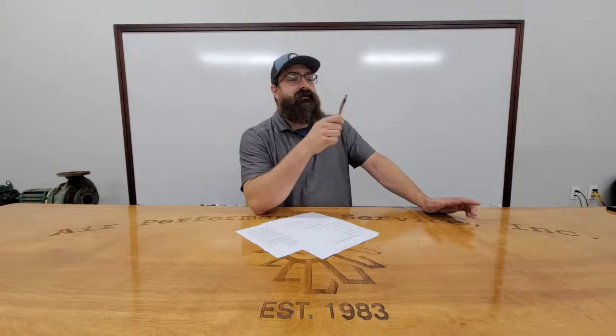Yes. So a lot of the older VFDs would be milliamp. The new stuff typically is standard DC voltage. You can switch them, and you can on a lot of the older ones. You just have to know where to go. Some of them, like an ABB, is a dip switch and a setting in the controller, at least on the 550s. I don't know about the 580s. It's only the dip switch now.